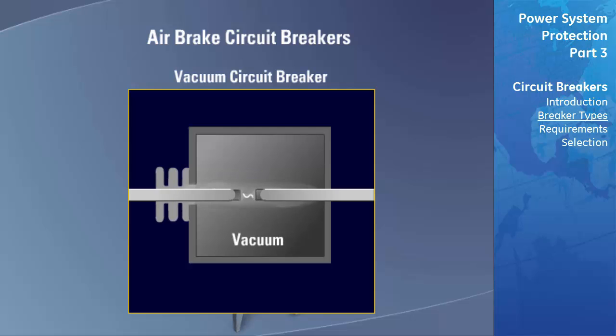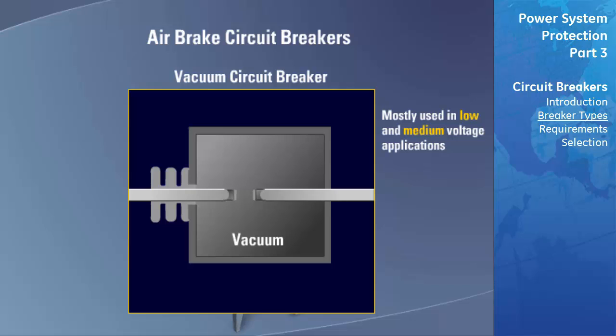A vacuum circuit breaker utilizes a vacuum to extinguish arcing when the breaker is opened and to act as a dielectric to insulate the contacts after the arc is interrupted. Vacuum circuit breakers are mostly used in low and medium voltage applications. Due to the high dielectric strength of a vacuum, the interrupters and gap between contacts are small, and the sealed interrupting chamber is made of porcelain.